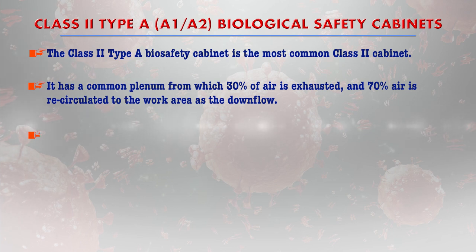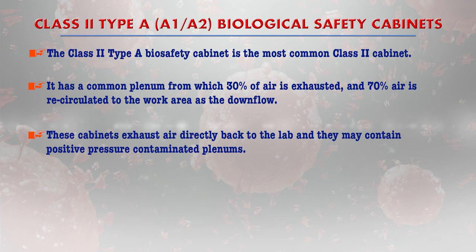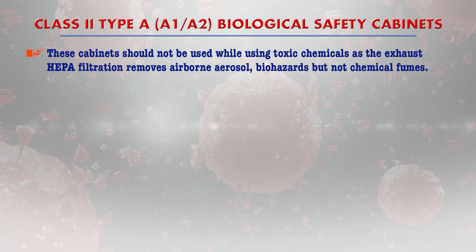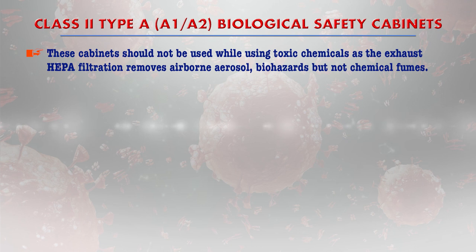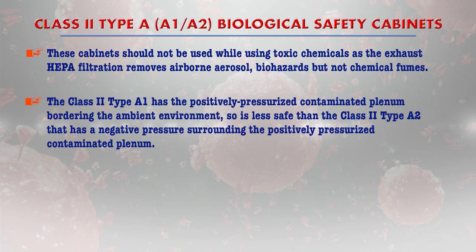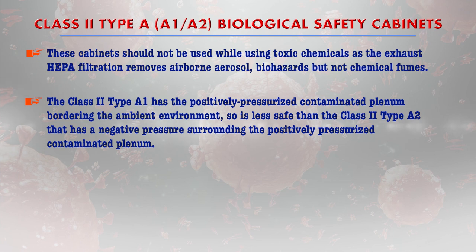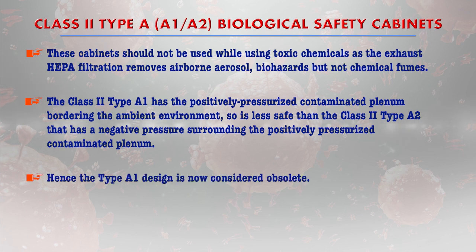Class 2 type A cabinets exhaust air directly back to the lab and may contain positive-pressure contaminated plenums, so they should not be used with toxic chemicals, as exhaust HEPA filtration removes airborne aerosol biohazards but cannot remove chemical fumes. The class 2 type A1 has a positively pressurized contaminated plenum bordering the ambient environment, making it less safe compared to type A2, which has negative pressure surrounding the positively pressurized contaminated plenum. Hence, the type A1 design is now considered an obsolete model.